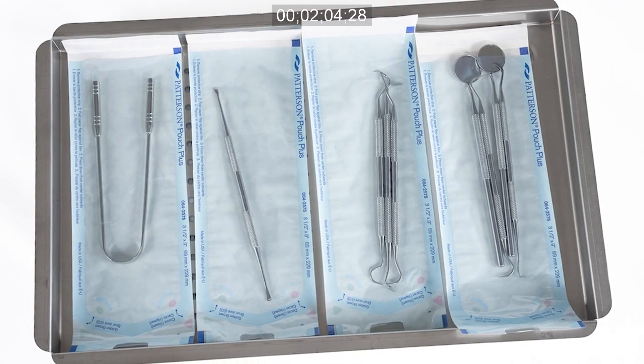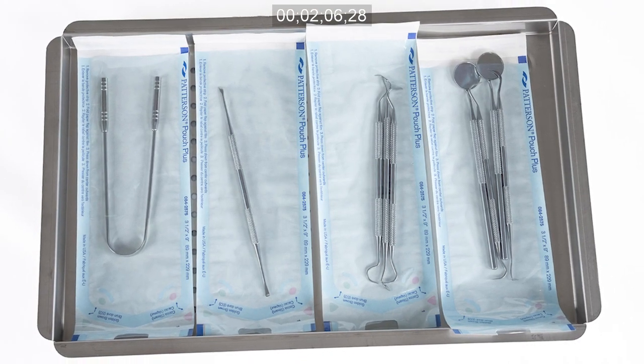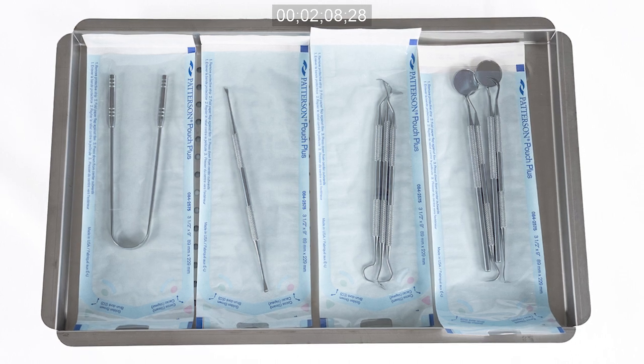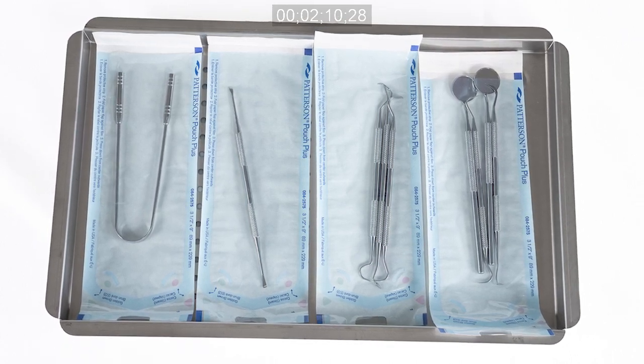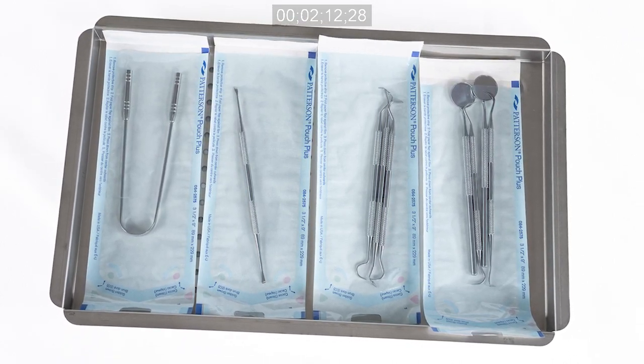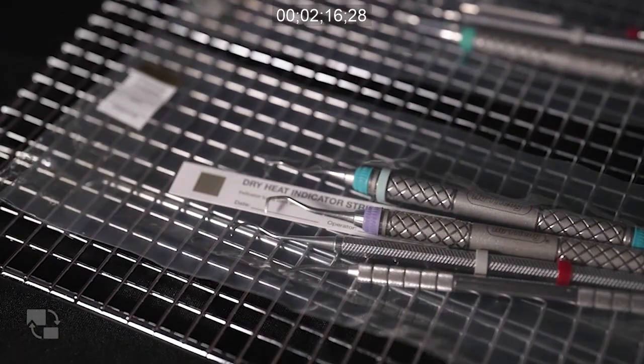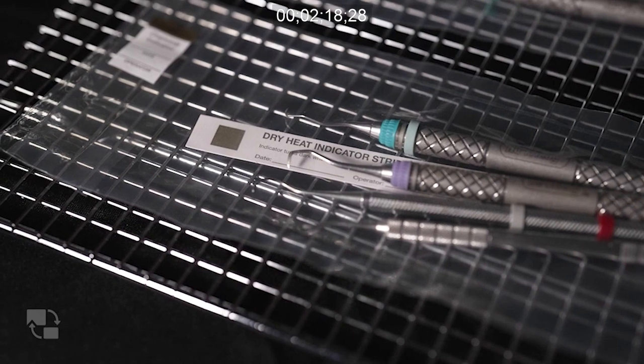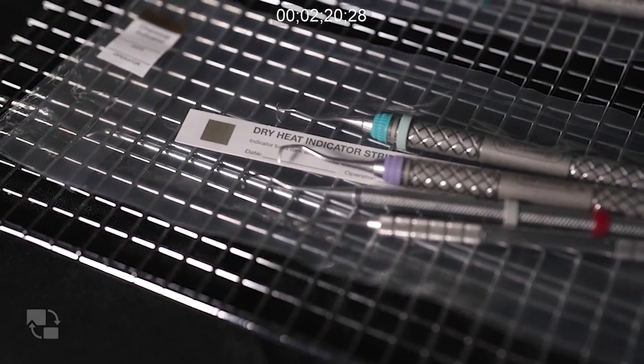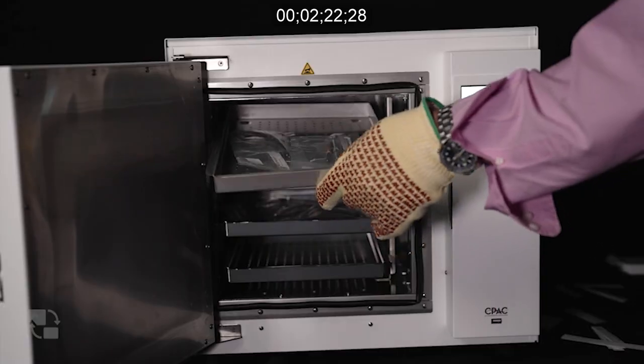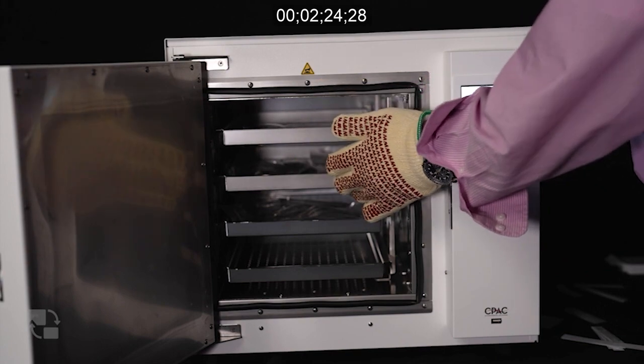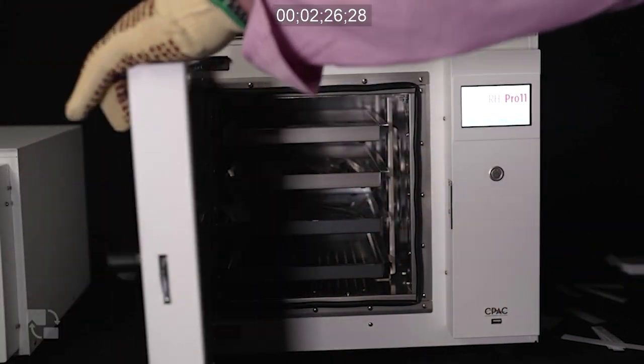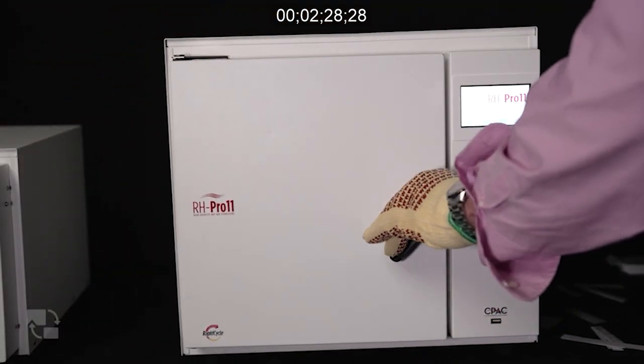In sterilizing at any one of the low-temperature cycles, you can either use high-temperature dry heat pouches and wrap, or steam sterilization pouches and wrap. Use dry heat chemical indicator strips or sticker labels in the sterilization load to confirm exposure to sterilization conditions. After loading the chamber, close the door, making sure the door handle is in its full locking vertical position.